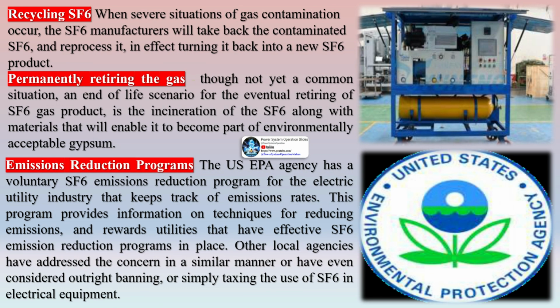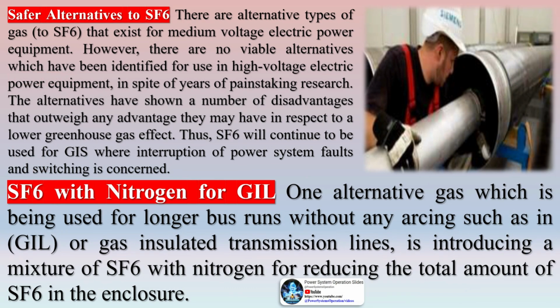Recycling SF6. When severe situations of gas contamination occur, the SF6 manufacturers will take back the contaminated SF6 and reprocess it, in effect turning it back into a new SF6 product. Permanently retiring the gas. Though not yet a common situation, an end-of-life scenario for the eventual retiring of SF6 gas product is the incineration of the SF6 along with materials that will enable it to become part of environmentally acceptable gypsum. There are alternative types of gas to SF6 that exist for medium voltage electric power equipment.